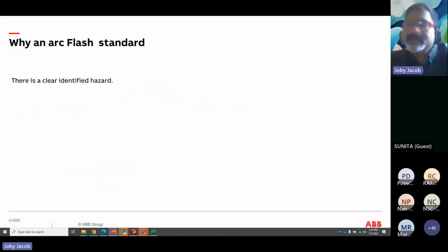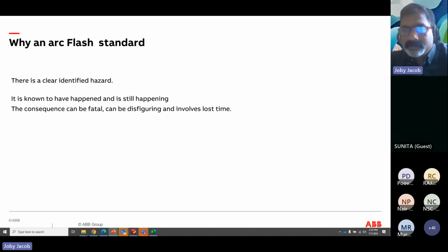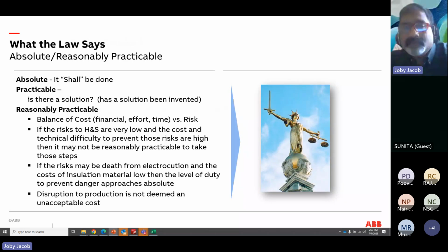For arc flash mitigation, we noticed that a clear hazard has been identified. It has happened and it is still happening. The consequences can be fatal, can be disfiguring, and involve lost time. So what does the standard say? The law says that as far as reasonably practicable, it shall be done, or a practical solution is there. Again, it's a reasonable balancing of cost, financial effort, and time. So if the risk may be death from electrocution and the cost of insulation material is low, then the level of duty to prevent the danger is absolute, and deferral of production is not deemed an unacceptable cost.